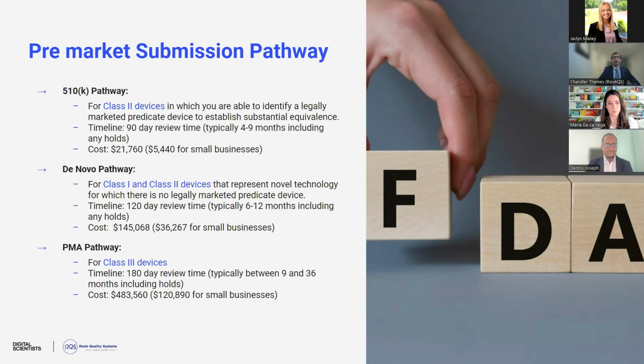So when we say holds, that's FDA essentially pausing the clock, asking questions, and you have up to 180 days to provide any sort of additional information they may request. So that 180 days seems like a lot of time, but depending on the things that the FDA is asking for, it can go very quickly. So for example, if they're requesting a retest or anything like that, you have to acquire different samples to help support that retest, or if there's any other third-party assessments that might take some time, that 180 days can fly right by. So it's very important that when you're submitting that initial submission, that everything is buttoned down and good to go.